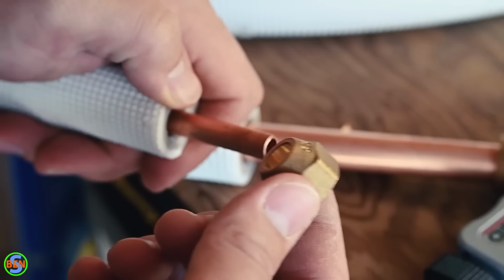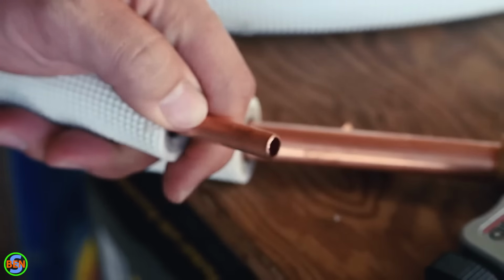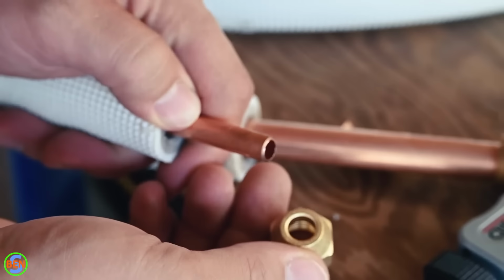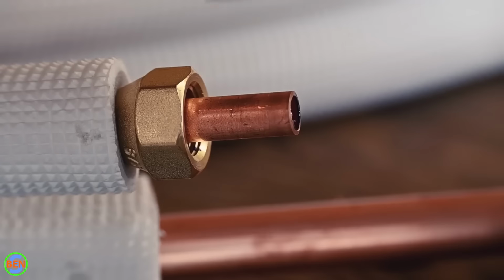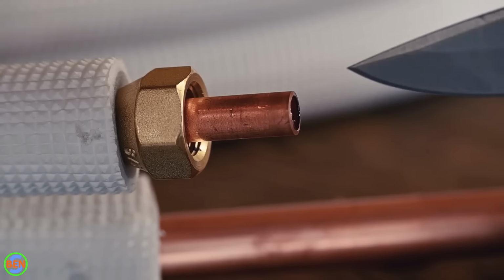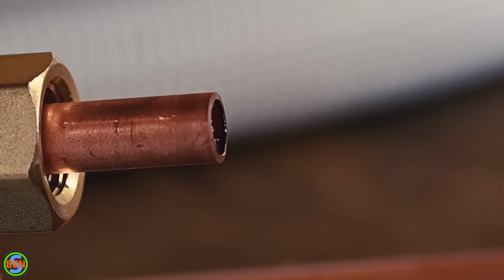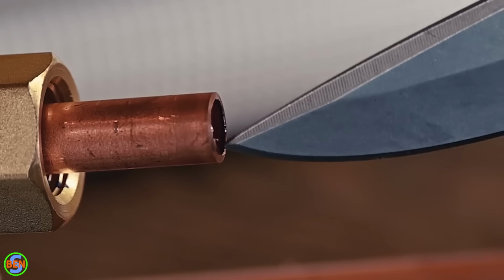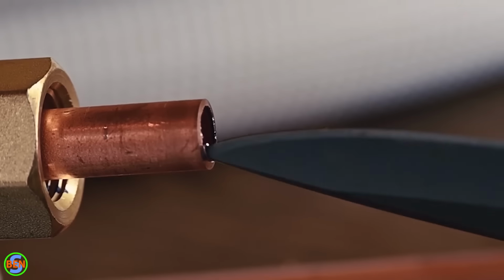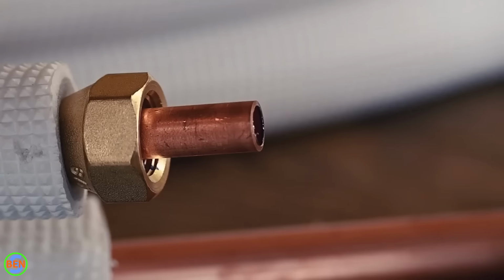Now we can remove the flare nut that came with this line set, and then we'll get the flare nut that came with the mini split. Now that our flare nut is in place, we are ready to deburr the inside of this pipe. You can use a deburring tool, or you can even use a knife to carefully remove that burr on the inside of the pipe and make sure that the burrs don't fall into the pipe.